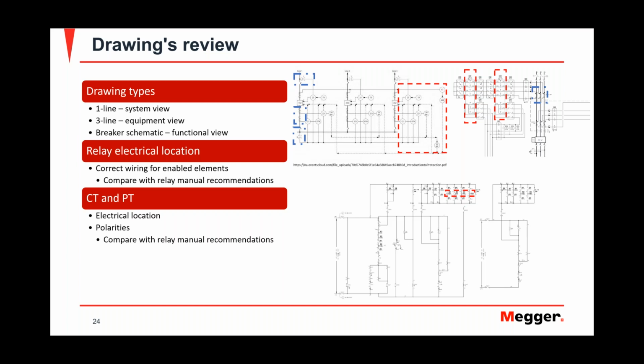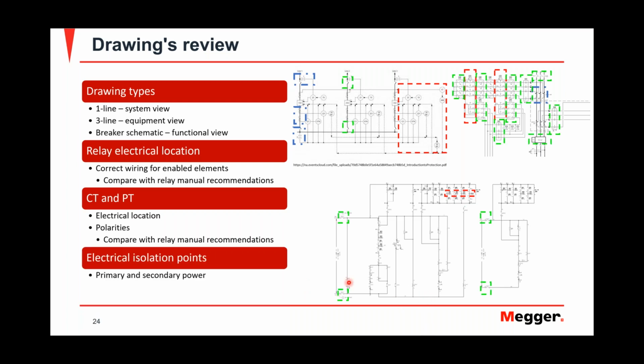You know where your CTs and PTs are located. This could help you look at the polarities on the PTs and the CTs. Maybe you don't see it on the one line, but you may see it on the three line. You obviously don't see that on the schematic. And your electrical isolation points. In the system view, knowing where the primary power is coming in: am I isolated from primary power?